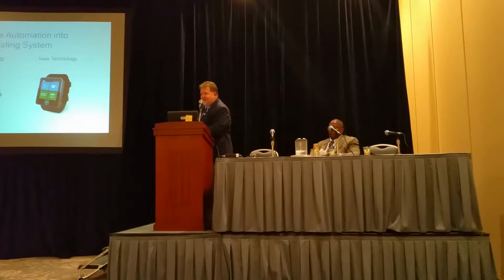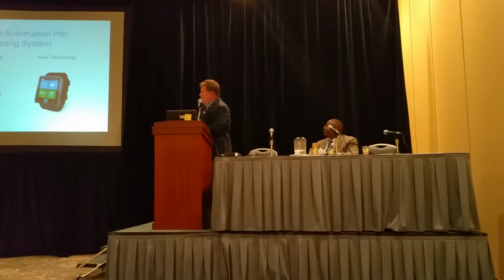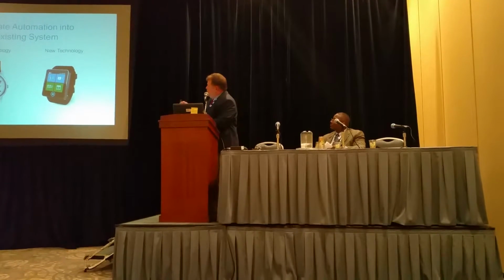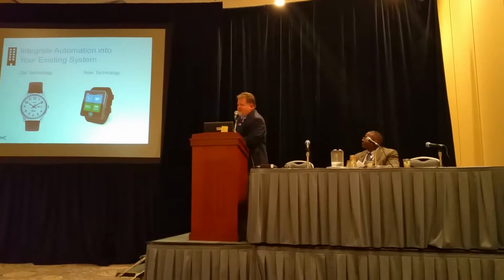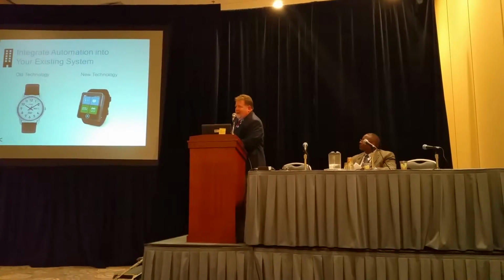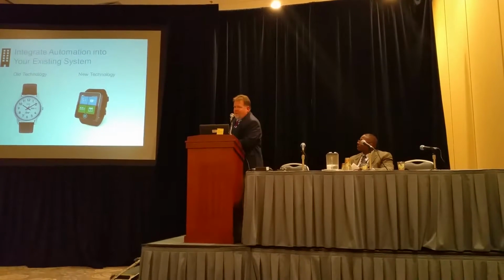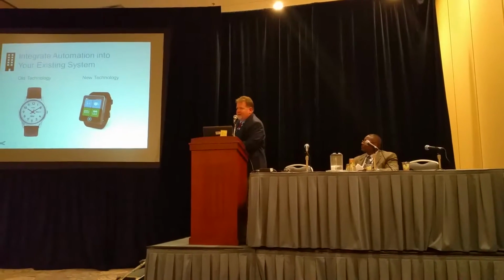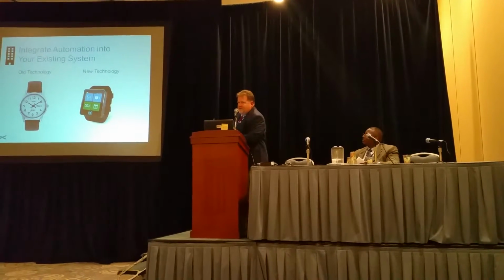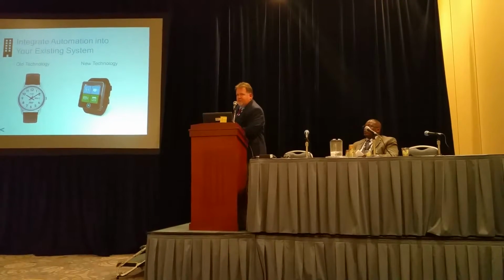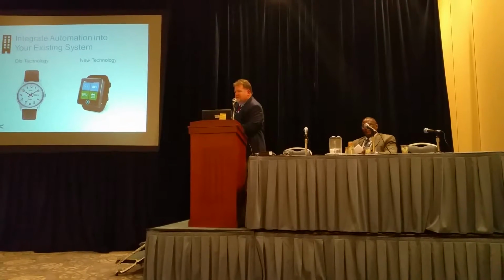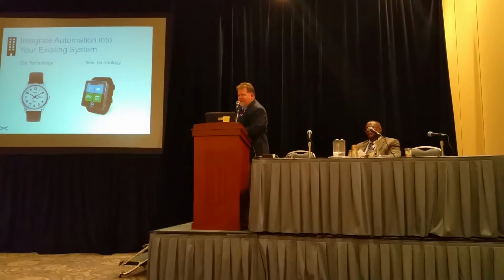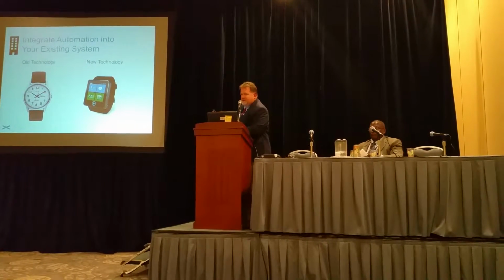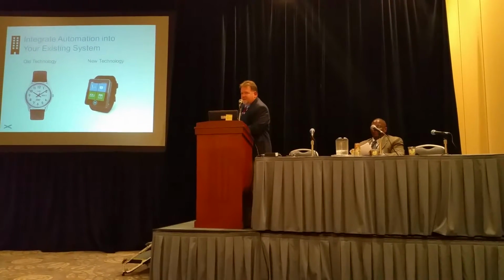So, integrating automation into your existing system. Now the watch on the left is a Timex watch. There's absolutely nothing wrong with it. That could be 30, 40 years old, and that's old technology. We have the watch on the right, which is a new smartwatch, and they both tell time. Just as your old system that you have, be it pneumatic or electro-pneumatic, is still controlling your HVAC, but we can integrate the new technology with the old. So to be clear, you currently have a control system on any piece of equipment that you have. How you integrate it with the new to give you optimum energy savings is the direction that you're going to want to go.